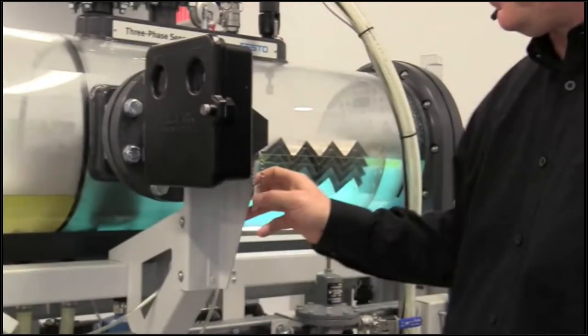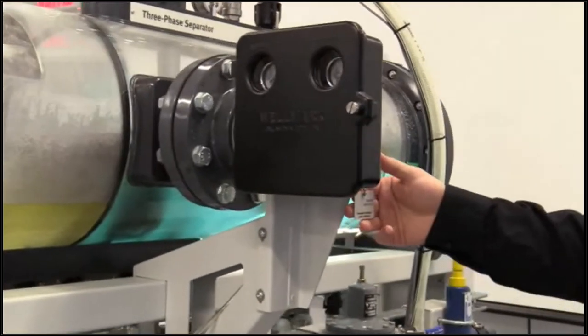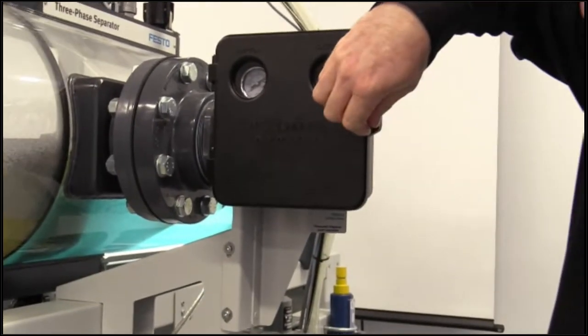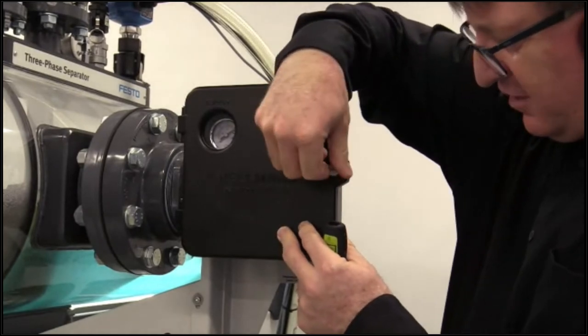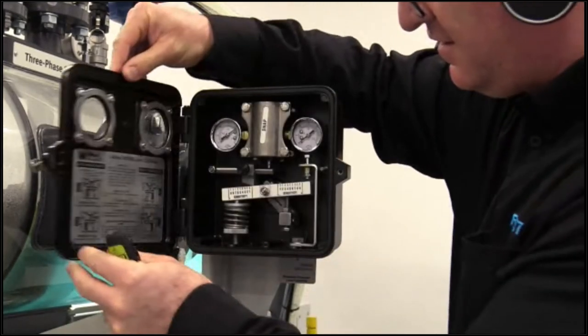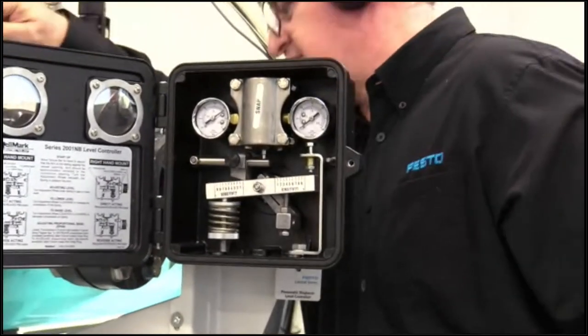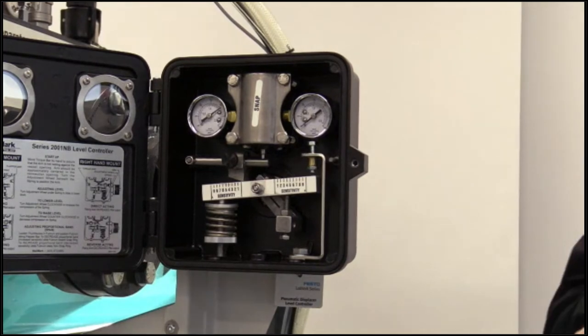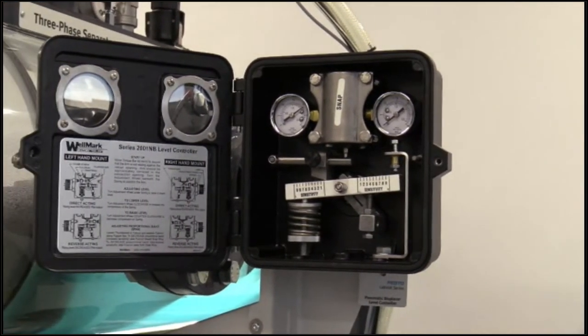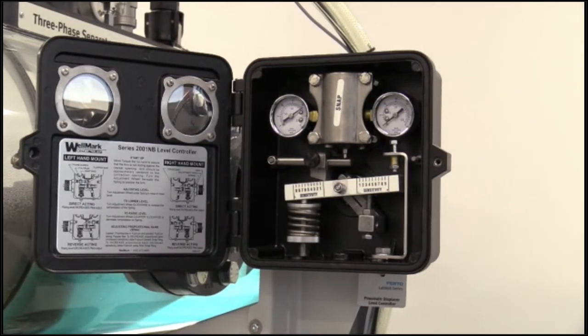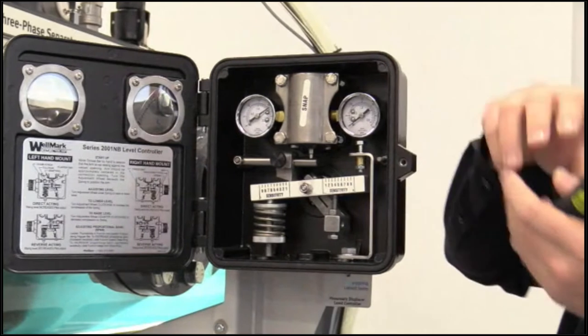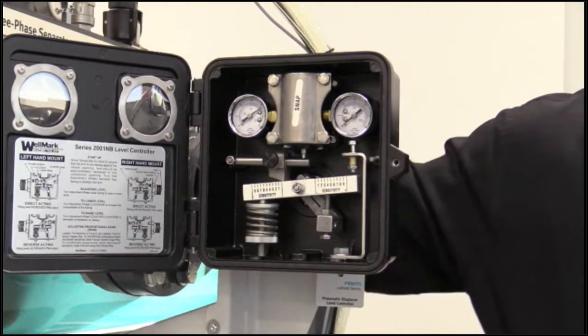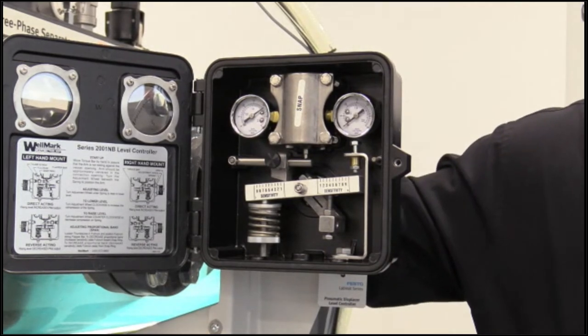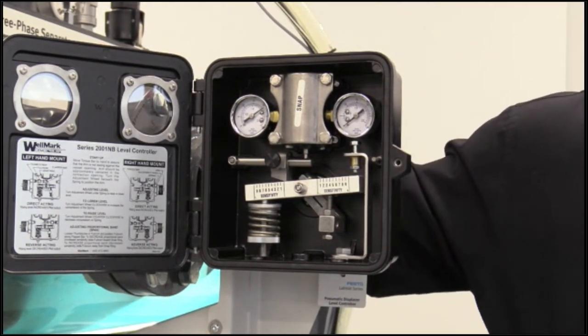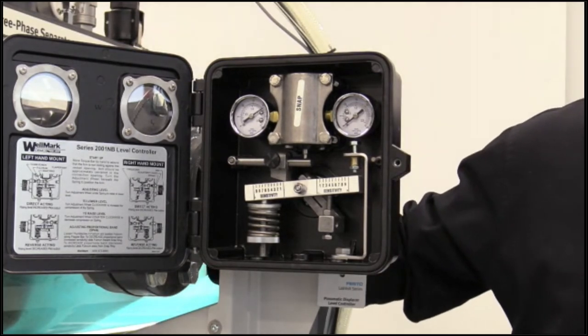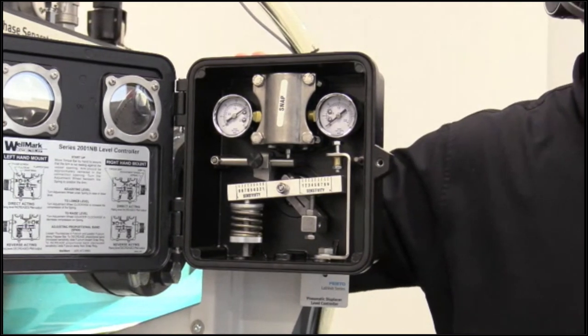Here we have this big device that is the pneumatic displacement level controller. So we have a fancy float here. We're going to open it. We have a float that right now is basically floating in the middle of oil and water. So now the float is in neither oil nor water. With this mechanism, we're going to change basically the density of the float. So we're going to calibrate it to actuate exactly at a certain level or a certain mix of water and oil. This is the same device that we have in a real three-phase separator.